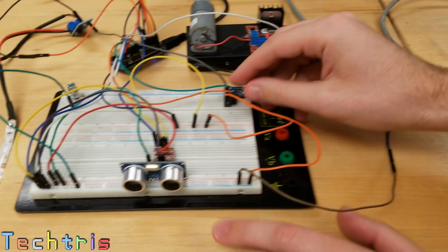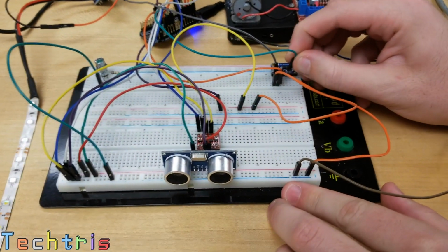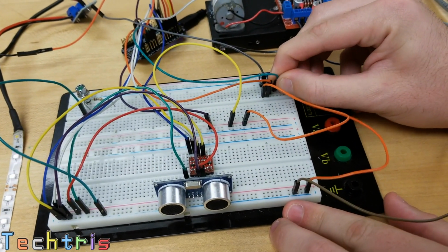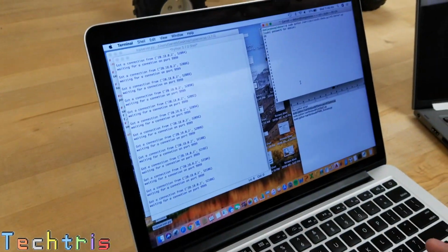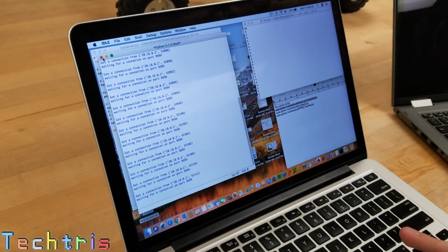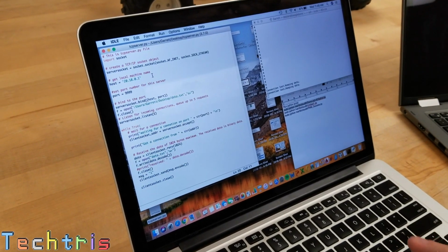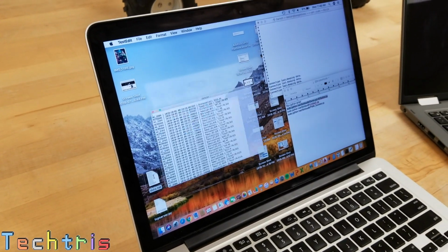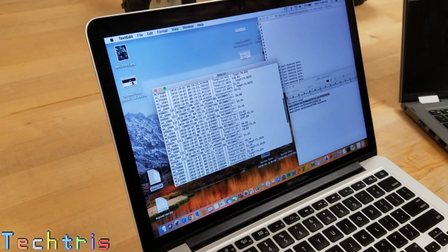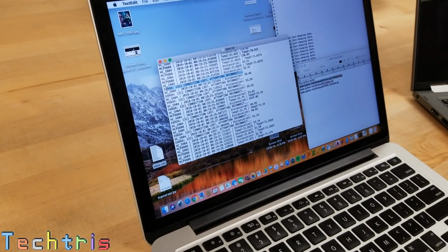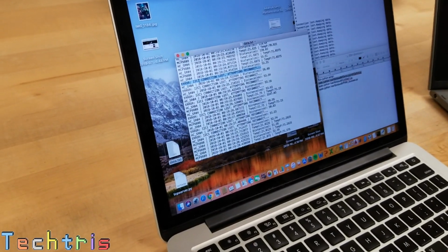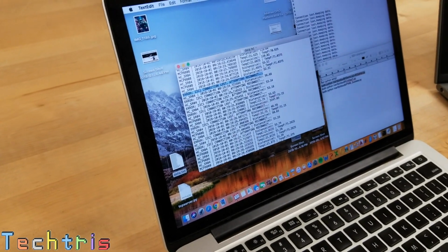We're going to go over here, unplug one of the connections for I2C, plug it back in, we can unplug it, plug it back in again. Okay, so then we can go over here and we can, let's just stop our server very quickly. And then we could take a look at the data file, go down, and so right here we could see where we lost the I2C1 connection, so it tells you exactly which port lost that connection.